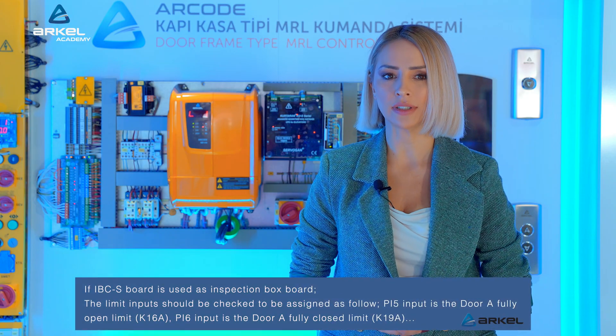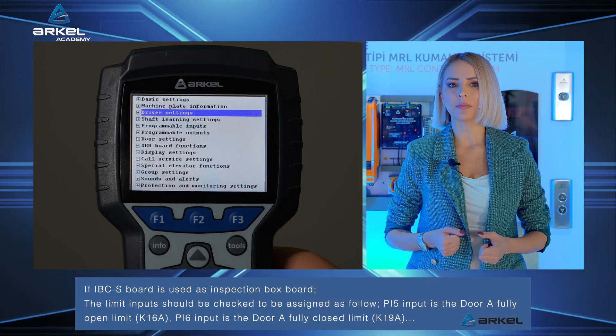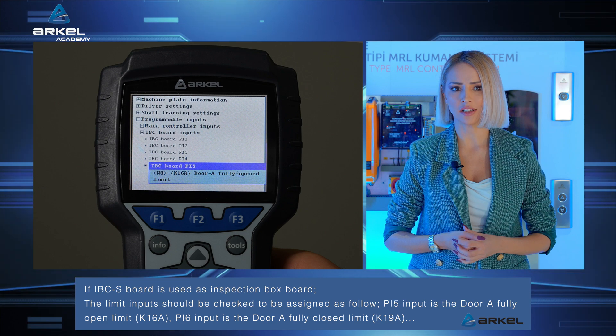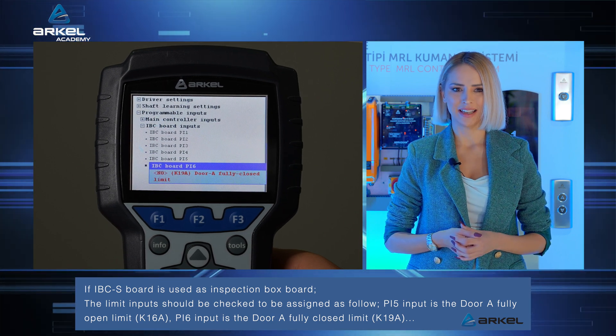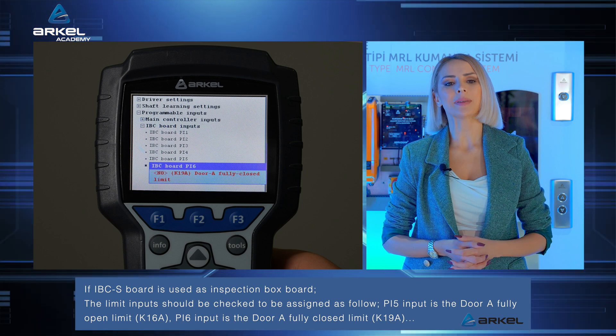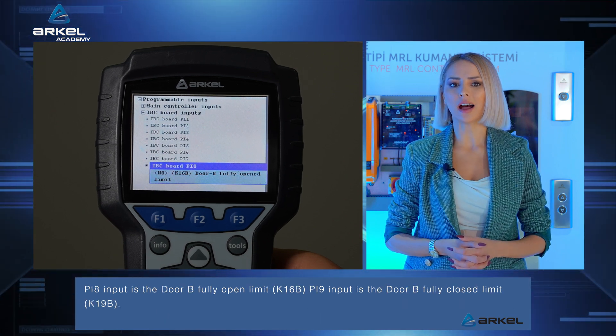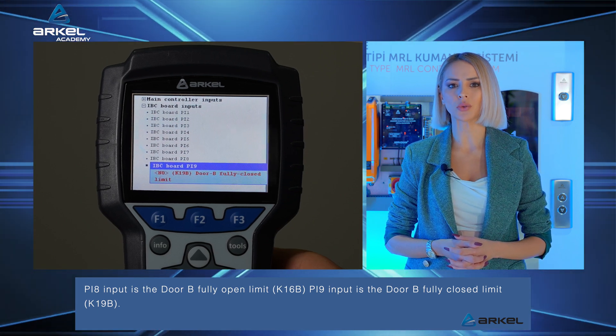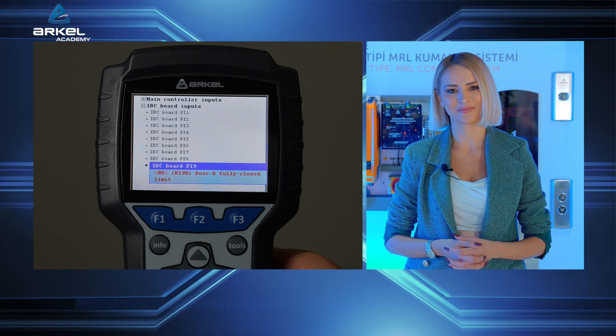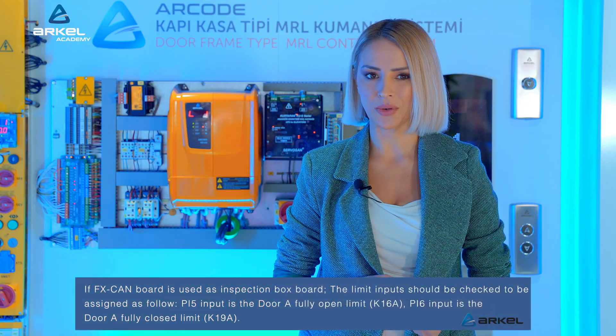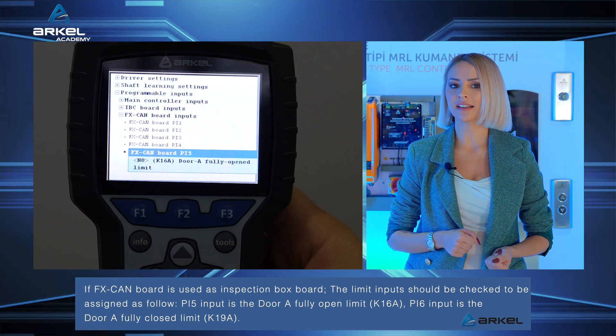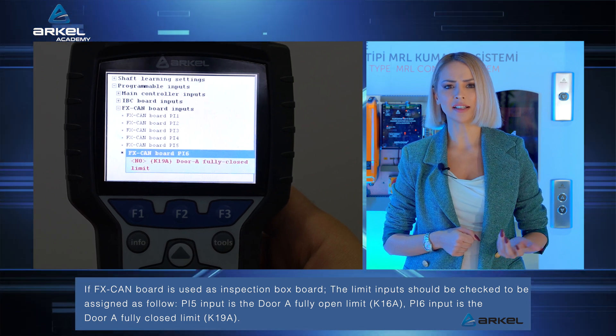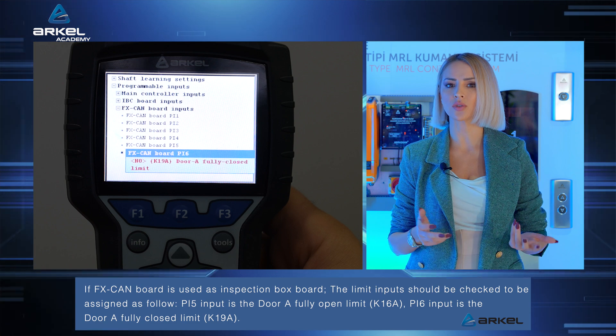If the IBC board is used as inspection box board, the limit inputs should be checked to be assigned as follows: PI5 input is the door A fully open limit, and PI6 input is the door A fully closed limit. If the FX CAN board is used as inspection box board, the limit inputs should be checked to be assigned as follows: PI5 input is the door A fully open limit, and PI6 input is the door A fully closed limit.